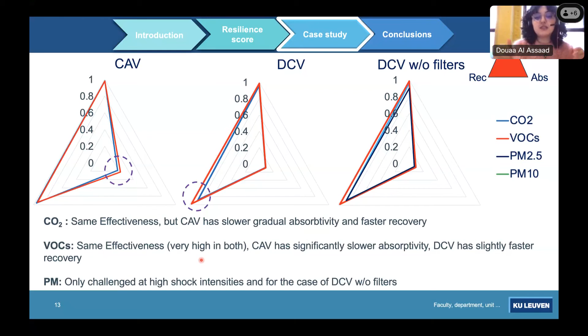As for VOCs, we noticed that they had the same very high resilience effectiveness in both systems. That's because with VOCs, when it comes to internal disruptions, we do have an increase in the emission rates, but this increase in pollutant load of VOCs is not as pronounced as in the case of CO2, which is why we don't see much effect on the resilience performance. And finally, particulate matter was only challenged in the case of DCV without any filters at higher shock intensities. So how does this translate to the resilience score?